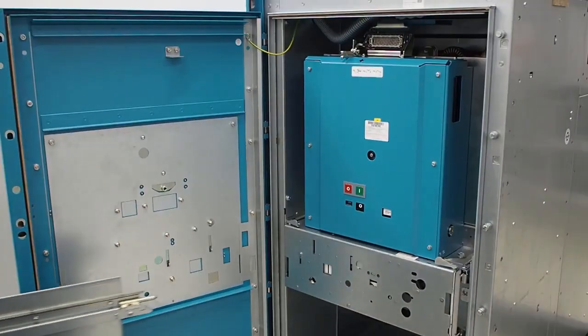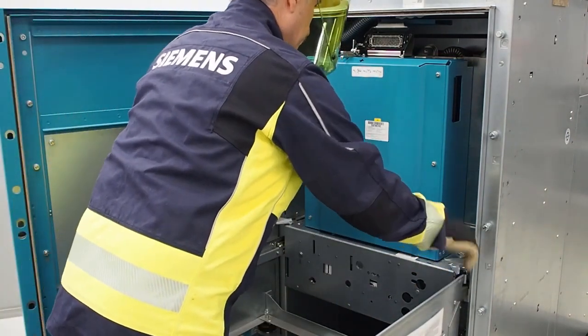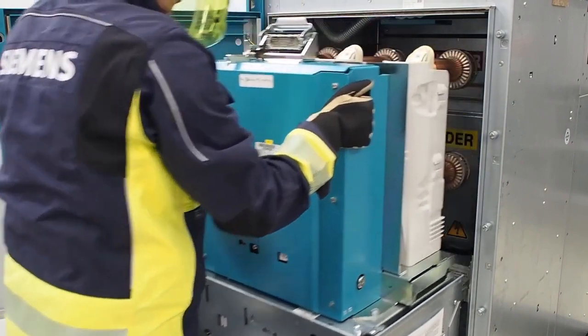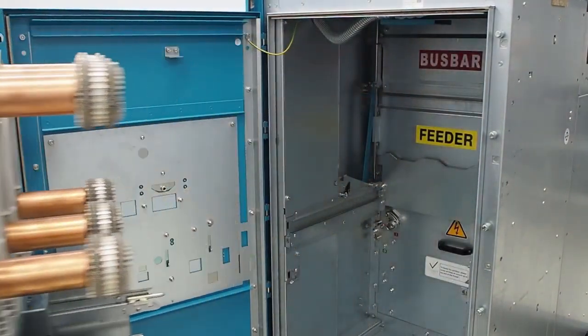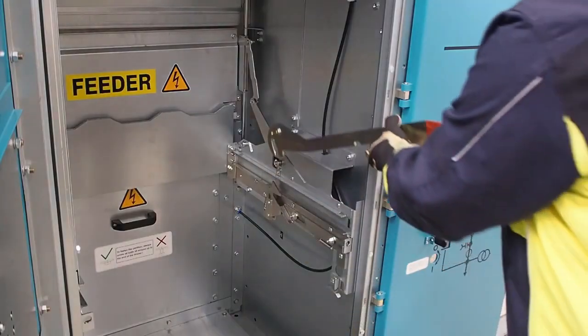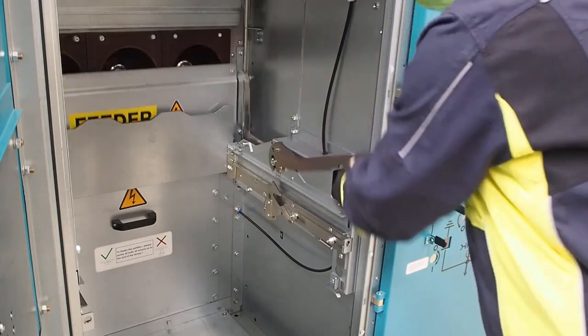Then, remove the circuit breaker from the panel with a service truck. Open the lower shutter of the feeder and check if the high-voltage tester works properly.